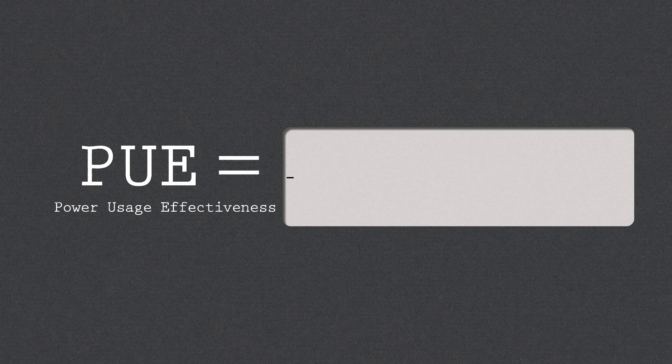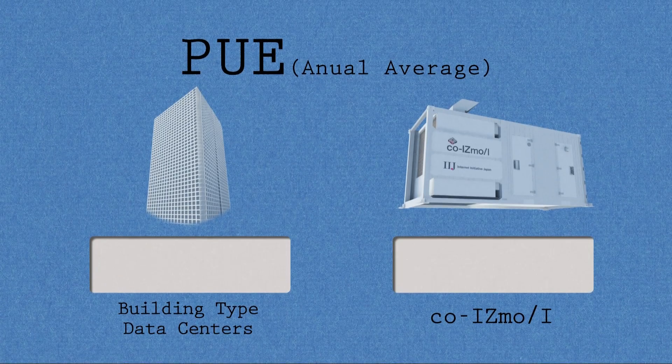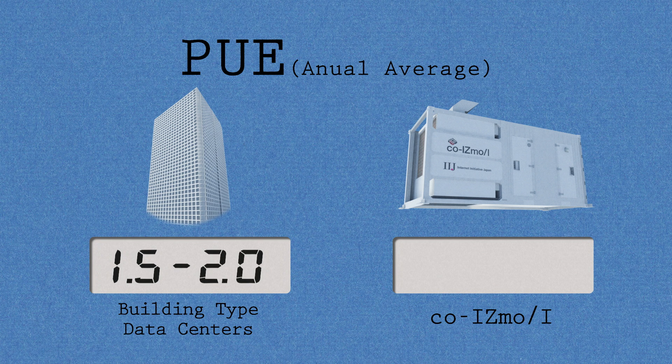PUE is an indicator commonly used to measure energy efficiency for data centers. The average PUE for building type data centers is around 1.5 to 2.0. co-IZmo/I's partial PUE is 1.17. Lower the figure, the higher the efficiency.